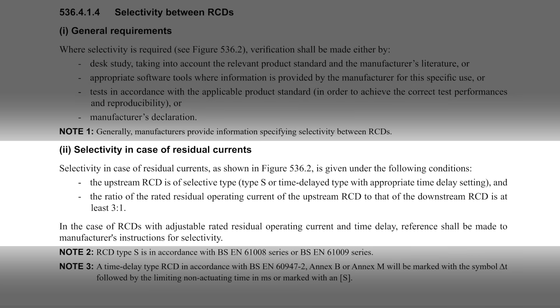Selectivity in case of residual currents as shown in figure 536.2 is given under the following conditions. It then outlines two requirements both of which must be fulfilled to be compliant. The upstream RCD is of selective type, type S, or time delayed type with appropriate time delay setting.